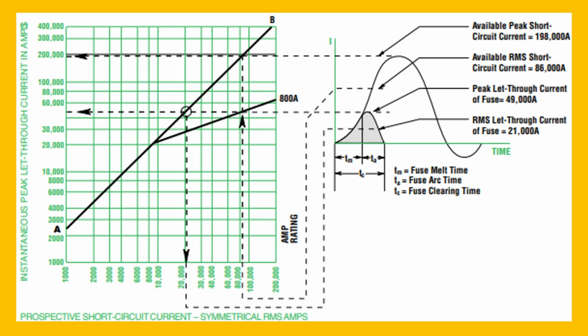This is an example of the up, over, down, Nintendo game that the engineers play. So you go up, over, down. So it's not just playing Contra and Nintendo, right? It's determining the peak let-through current. And this is how the engineers would do it. Basically, starting at the prospective short circuit current of 86,000 amps, proceeding up to the 800 amp fuse curve. Then they follow left to the instantaneous peak let-through current, and then read the peak let-through current at 49,000 amps. So if a fuse had not been used, the peak current would have been 198,000 amps.